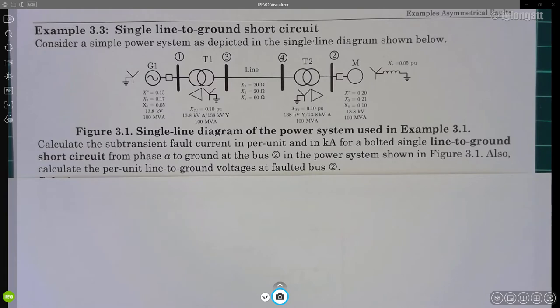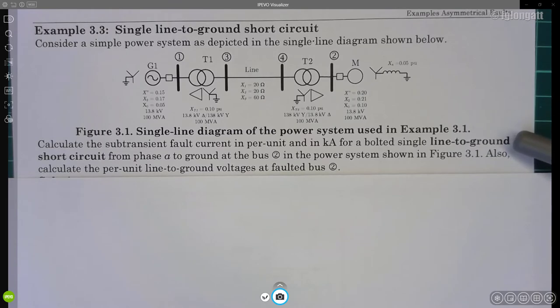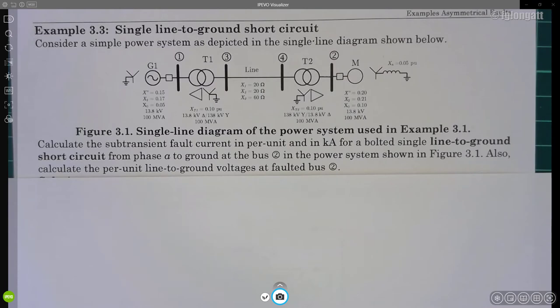The job today is to calculate the subtransient currents in per unit and kilo amps, considering a bolted single line-to-ground short circuit from phase A to ground at bus number two. The second question is to calculate the per unit line-to-ground voltages at the faulted bus two.